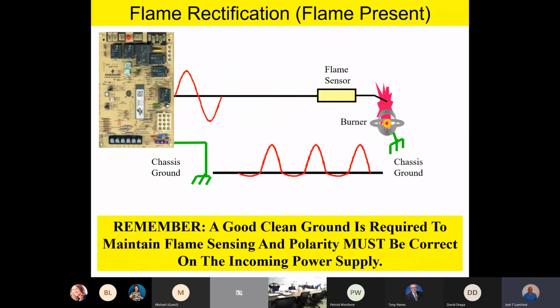Now, one very important thing to remember is that you have to have a really good, clean ground, and the polarity on the furnace has to be proper. If your hot and neutral are backwards, meaning the black and white wires are reversed on the power coming into the furnace, it will not be able to sense the flame. Those are the two big things we find a lot of times, especially in an older home: we don't have a good ground, or the installer gets the black and white wires mixed up. It won't burn anything up, but the point is it won't sense the flame. Polarity has to be correct, and you have to have a good, solid ground in order for this flame sensing circuit to work properly. Any questions or comments on this basic science of flame rectification? We'll get into measuring flame current in a second.